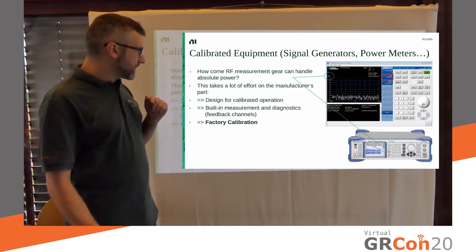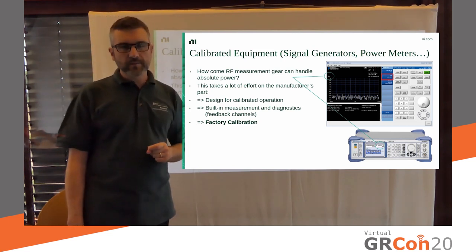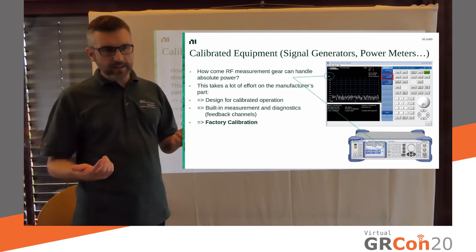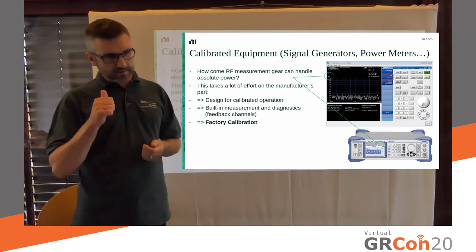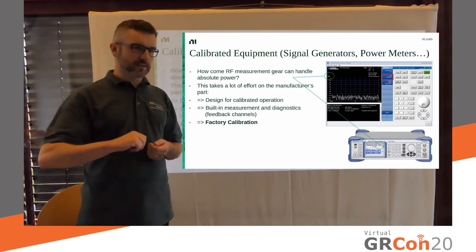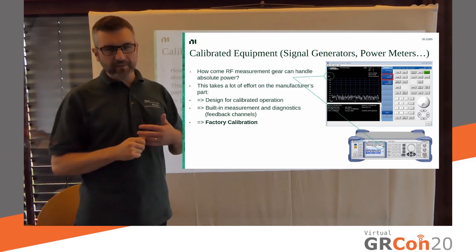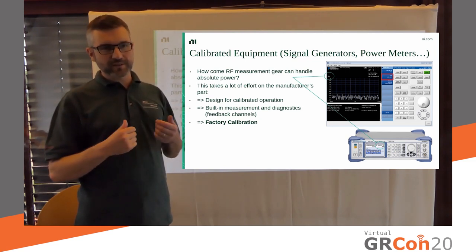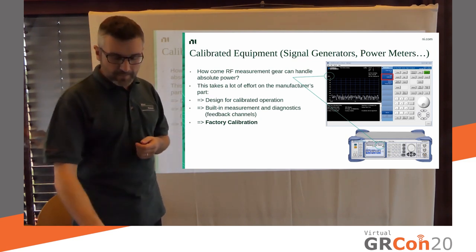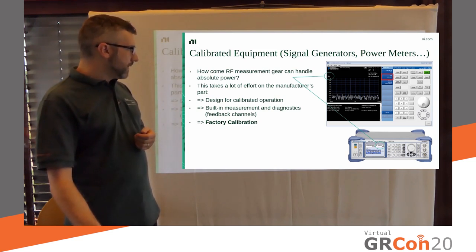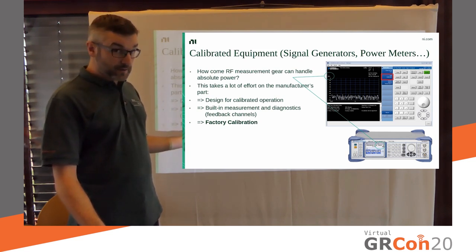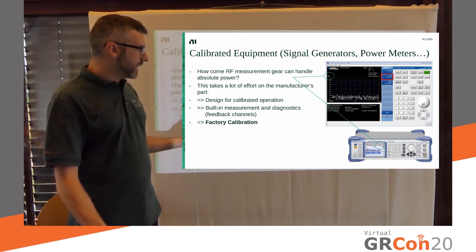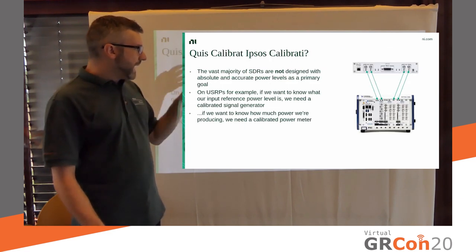But, most importantly, they do factory calibration. So, if you've seen that probably, you buy a new spectrum analyzer or something that has a sticker on it, says calibration valid until, well, on my devices it'll say October 2008 or something like that. So, factory calibration is a key piece of, a key piece of the, of the puzzle.